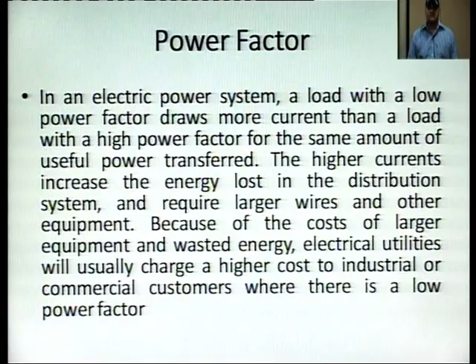Higher currents increase the energy lost in the distribution system and require larger wires and other equipment. So if the power factor of a system is low, then for the same power rating we must use larger wires with larger diameters, larger kVA rating transformers, and larger generators. This is the effect of low power factor: the cost of larger equipment and wasted energy. Electrical utilities will usually charge a higher cost to industrial or commercial customers with a low power factor, because they have higher energy costs and must implement larger equipment.